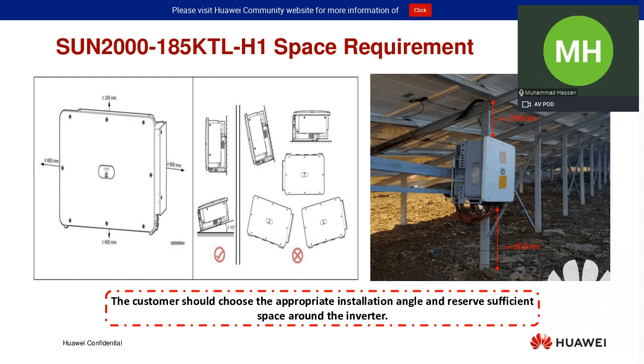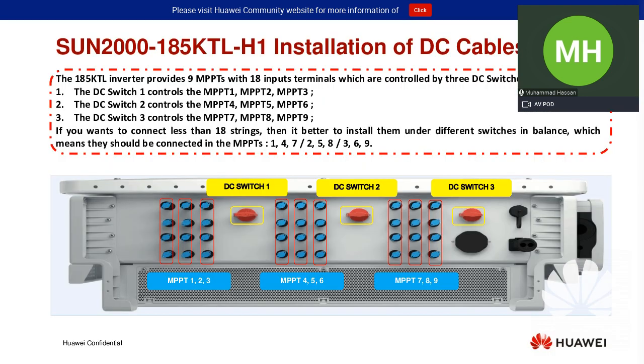On the right side, you can see the installation where the customer has followed our recommendations. They have provided 600 mm distance from the bottom, from the ground, and 200 mm from the top of the mounting frame from the solar panels, so that the heat will be dissipated from this inverter. The 185 KTL comes with 9 MPPTs and 18 inputs. All 9 MPPTs are controlled by 3 different switches. As you can see in the picture, MPPT 1, MPPT 2, MPPT 3 are controlled by DC switch 1. Then MPPT 4, 5, and 6 are controlled by DC switch 2. MPPT 7, 8, and 9 are controlled by DC switch 3.